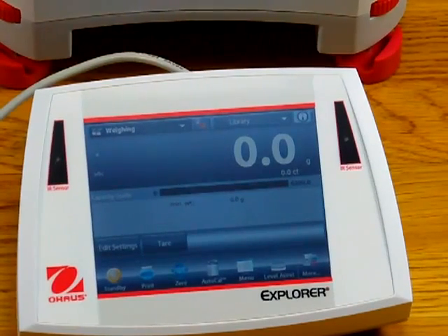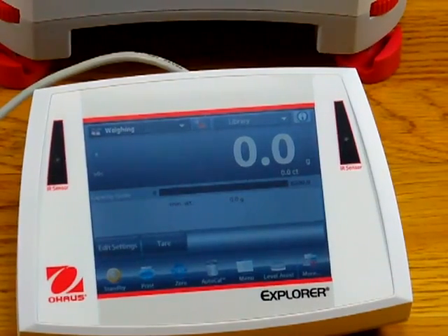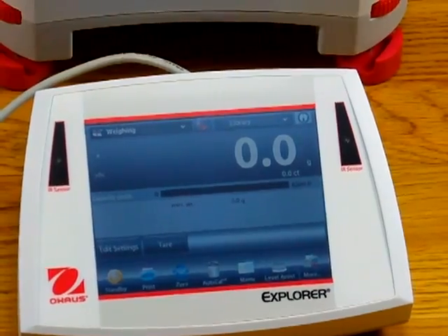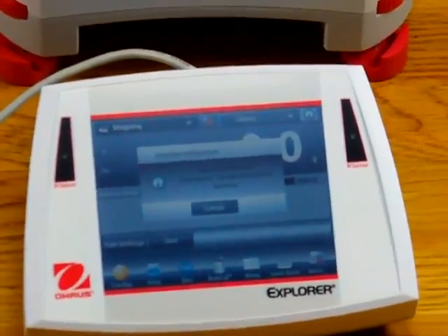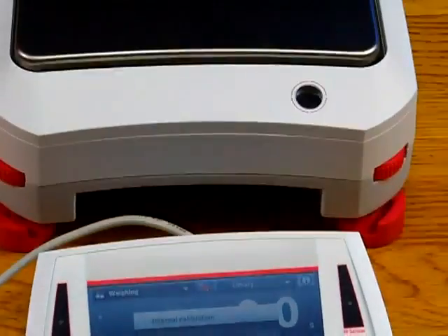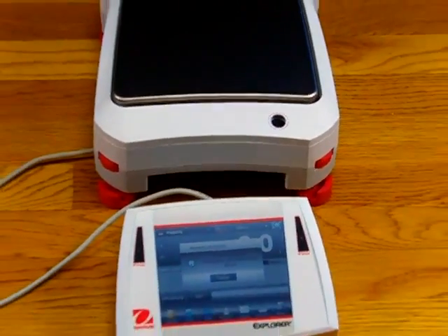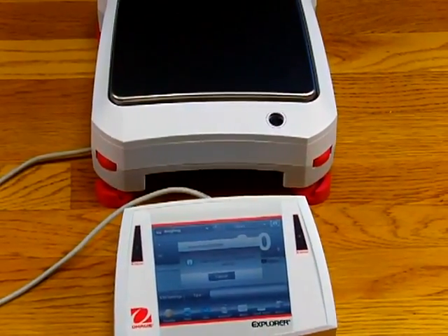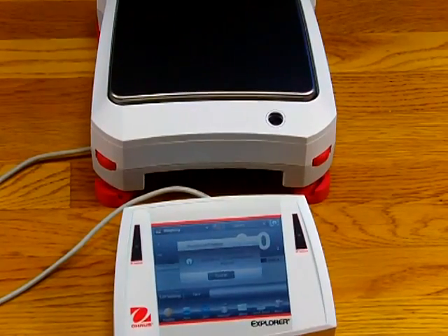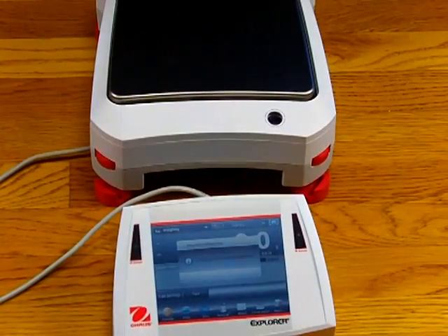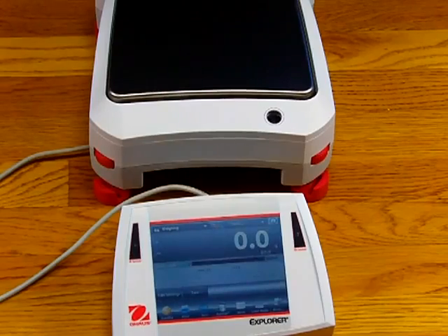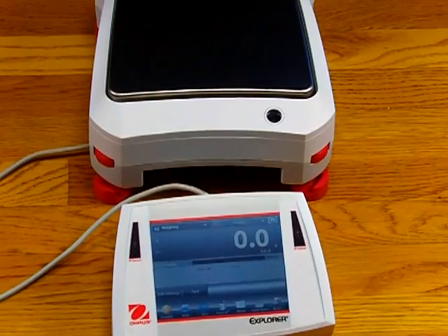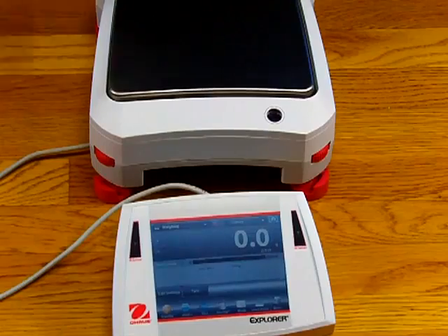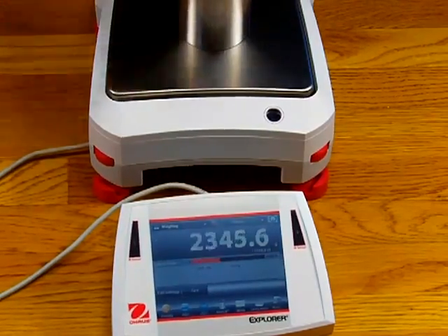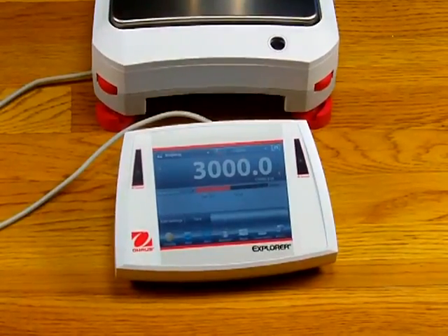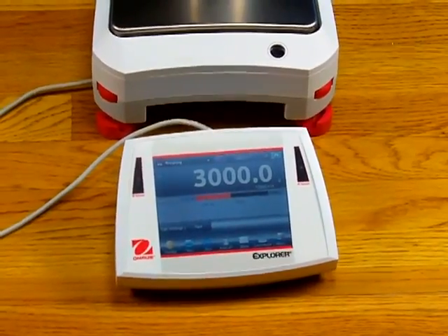Now the balance base also has 2 sensors on the right and left, and this sensor here we've set up so that if you wave over it, it will start the calibration for you. Ohaus's goal is to have the operator use the balance with as much ease as possible - no need to press some tactile button hard to calibrate. Everything is just a wave of the hand, and you can configure these sensors for optional functions. That's a real nice feature.